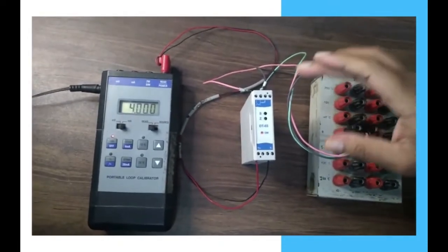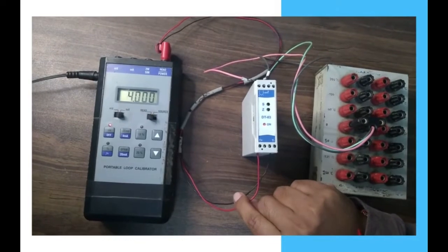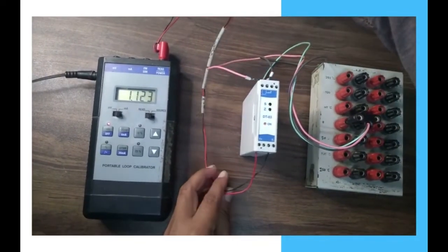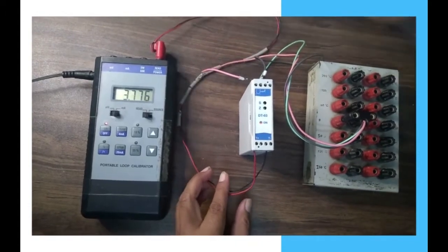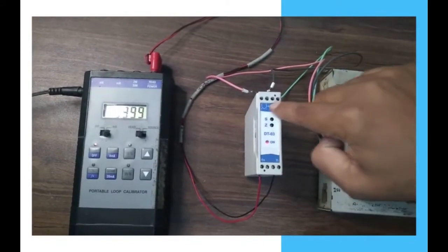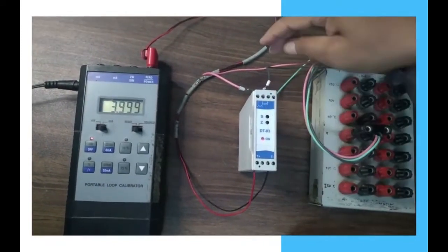Here we have applied a power supply of 24 VDC. This is a loop power device, so from these two wires we will get 4 to 20 milliampere current according to temperature variations. Here, from the RTD resistance source, we have applied the RTD 3-wire input.